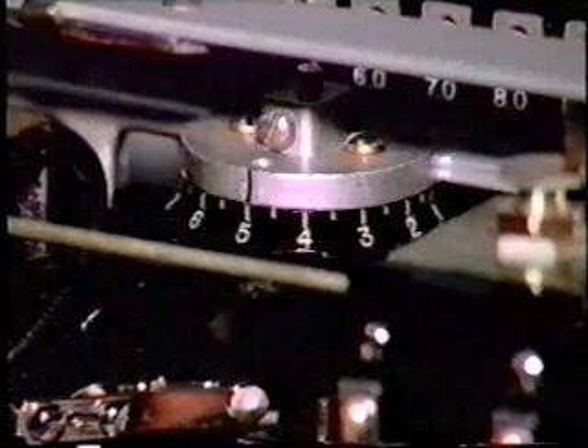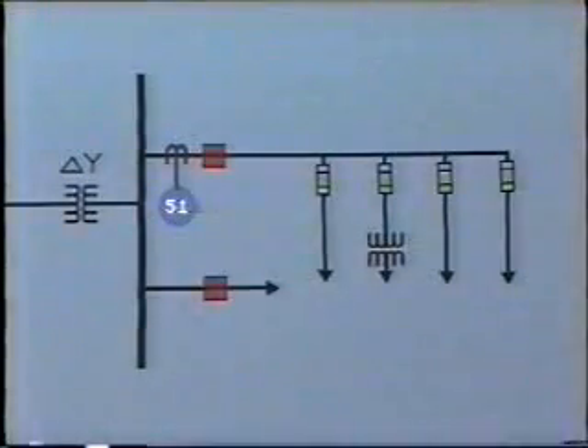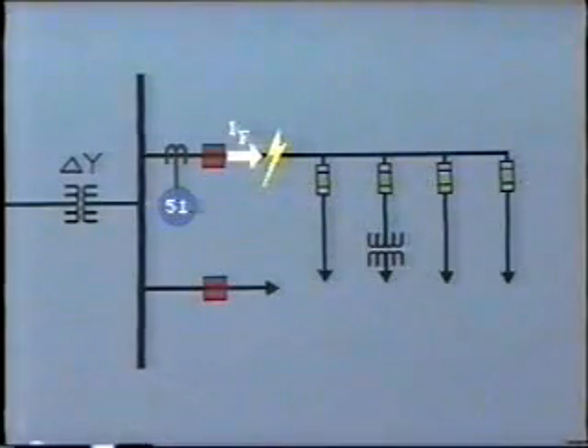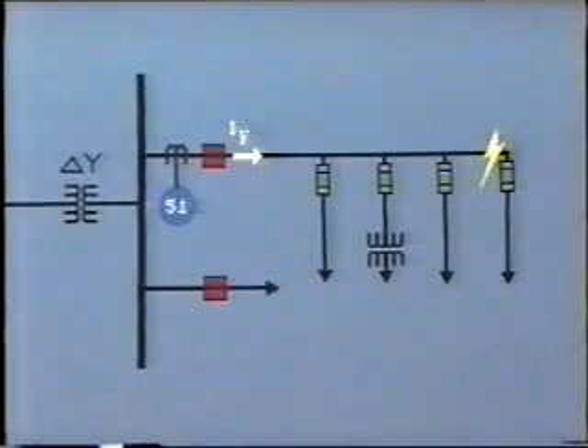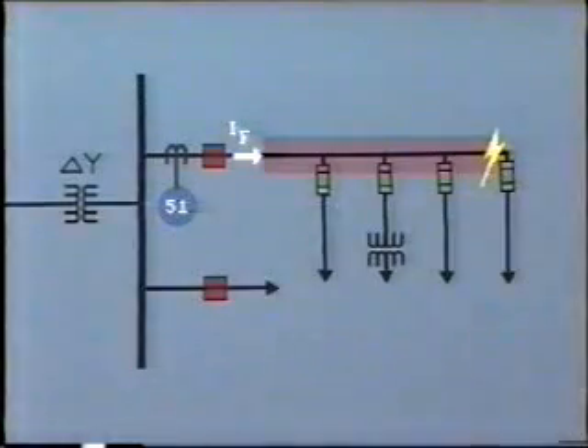In order to set the time dial of the relay, it's necessary to know the anticipated value of fault current for a fault close into the breaker and for a fault at the far end of the line. As we know, the level of fault current flowing to feed a short circuit at the far end of the line will be less than for a short circuit close in. This is because of the impedance of the line between the two points.